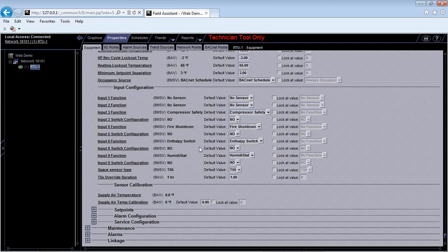None of these inputs are factory installed other than the enthalpy switch. That is the only one that you can actually get factory installed on this RTU Open controller. I take that back. I think you can get a return air CO2 sensor actually wired in, which would count as the IAQ sensor here. But something to note is, like I mentioned previously, this RTU Open controller I literally just took out of our warehouse, brand new, uploaded it. It comes defaulted with these inputs set up: compressor safety, fire shutdown, enthalpy switch. These sensors are not actually tied into it. This is just how the RTU Open controller program comes from the factory.